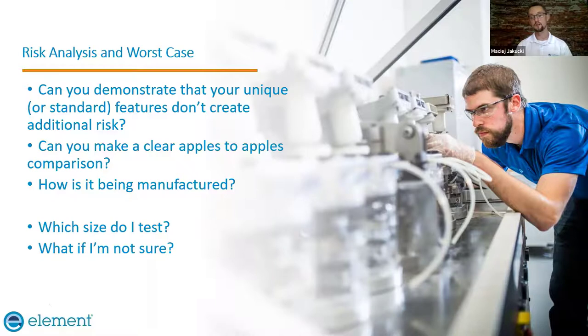There's nothing like calling a customer and telling them that this device they just spent nine months developing and manufacturing, after making this last second tweak, is now catastrophically failing. That's not a positive scenario to be in. But one of the things you want to pay attention to is making sure that when you're testing, it's the final design. Your worst case testing is done on the final piece, because even a small tweak, even just aesthetic, can make a big impact.